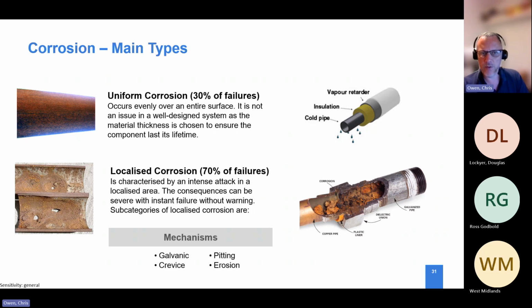And again, when we talk about uniform corrosion, normally within a pipework system, you'd expect to see some form of uniform corrosion take place initially. But once the oxygen is depleted, that system stabilizes and then it will just sit there nicely. Most of the concerns or issues we tend to see now are normally to do with corrosion on the outside of the tube. And that's taking place in a uniform manner because any insulation which has been put around the tube has got wet or damp, or there's moisture in there. And that means that you've got water and oxygen sitting on top of the tube, which obviously can break through any protective coating and cause corrosion.